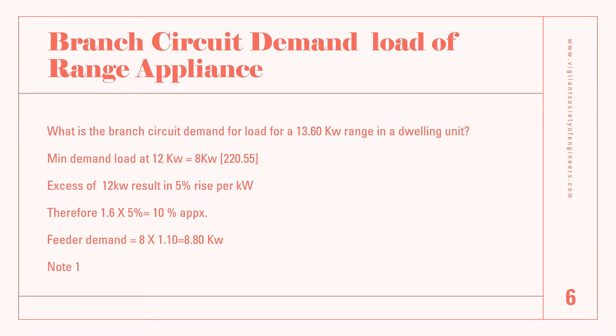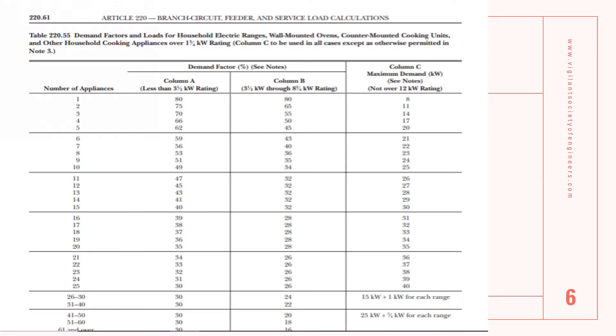Next question: what is the branch circuit demand load for a 13.60 kilowatt range in a dwelling unit? Using Table 220.55, we can only get values up to 12 kilowatt and we are limited from going in excess of that value in the table. So for a range of 13.60 kilowatt, we take the first 12 kilowatt from Table 220.55, and the demand for a maximum of 12 kilowatt is 8 kilowatt.